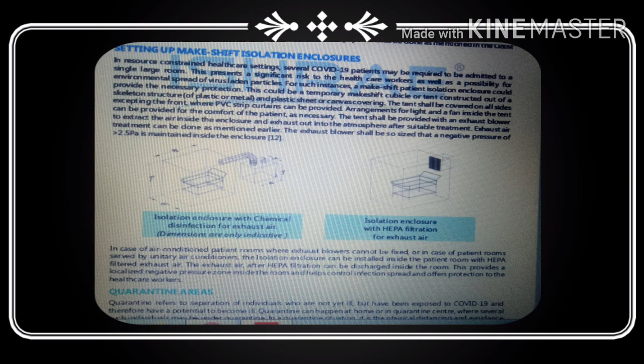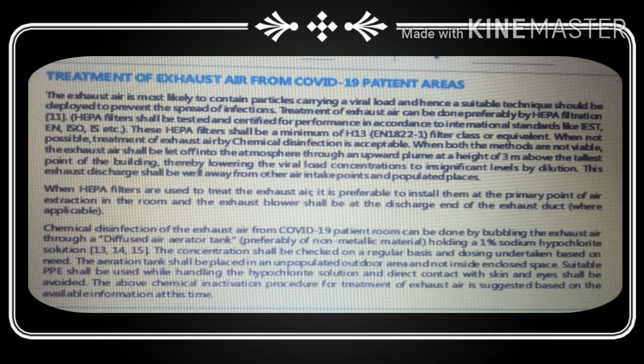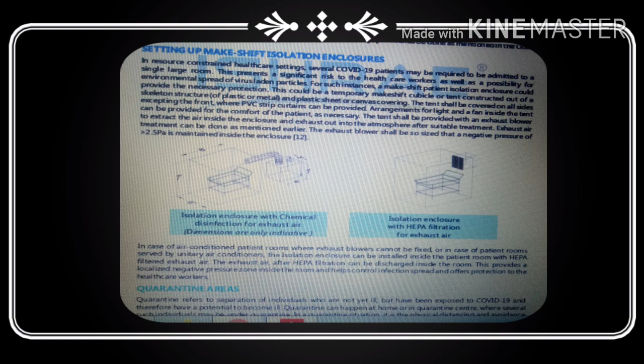Exhaust air treatment can be done as mentioned, and the exhaust blower shall be sized so that a negative pressure of about 2.5 pascals is maintained inside the enclosure. In case of air conditioned patient rooms where an exhaust blower can't be fixed, or in case of patient rooms served by a unitary air conditioner, the isolation enclosures can be installed inside the patient room with HEPA filtered exhaust air. The exhaust air after HEPA filtration can be discharged inside the room. This provides a localized negative pressure zone inside the room, helps control infection spread, and offers protection to the healthcare workers.